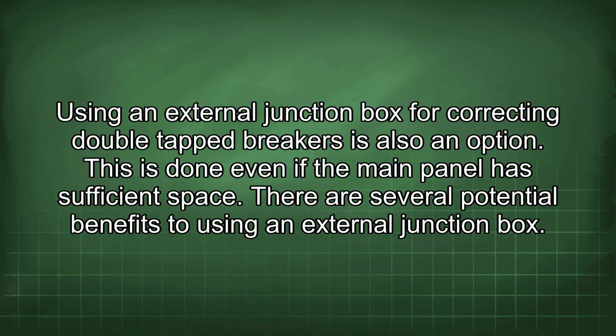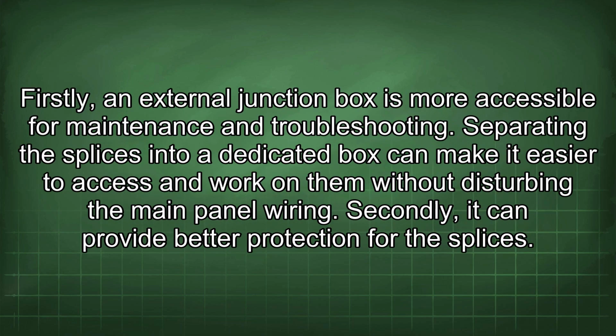Using an external junction box for correcting double-tap breakers is also an option. This is done even if the main panel has sufficient space. There are several potential benefits to using an external junction box. Firstly, an external junction box is more accessible for maintenance and troubleshooting. Separating the splices into a dedicated box can make it easier to access and work on them without disturbing the main panel wiring.